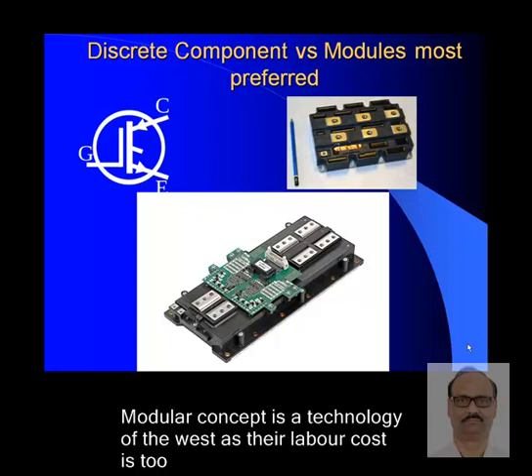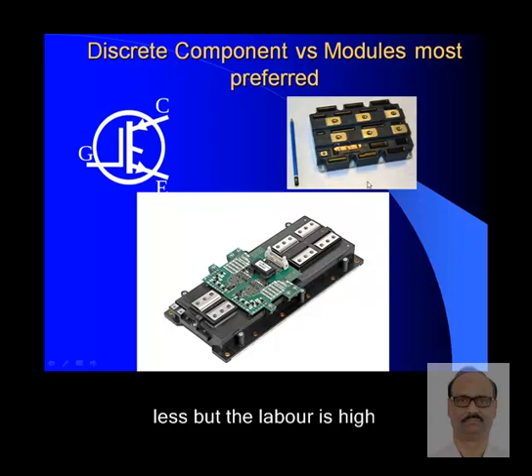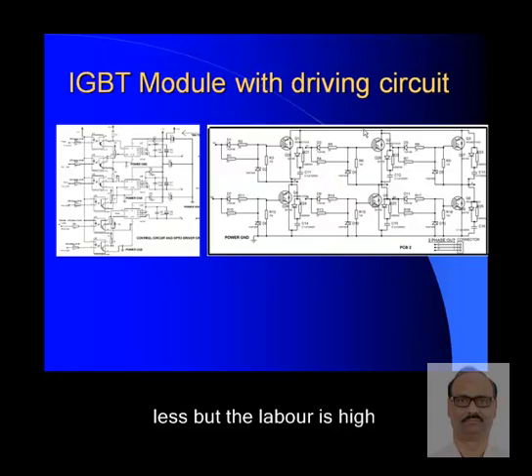Discrete components versus modules: modules are most preferred. A discrete IGBT is singular; you can use multiple discrete IGBTs to build any inverter. Alternatively, modules package six IGBTs into one unit, making it much easier to replace devices compared to wiring individual MOSFETs. The bottom of the module also acts as a heat sink. The modular concept is a technology of the West, where labor costs are high.